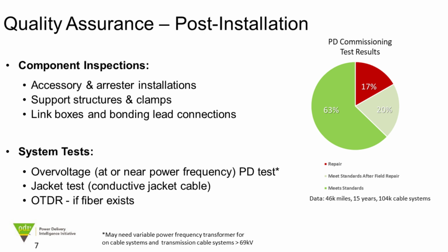This doesn't mean that every component that's not meeting the industry expectations on installation is going to fail right away. In fact, we are looking at 30 to 40-year-old cables that are still going to failure with defects in them caused by installation. So these defects can take a long time, even decades, to go to failure.